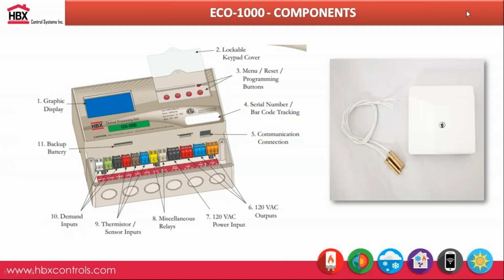In terms of key components on the 1000, as you see, we have a full graphic display. The nice thing about the Eco 1000 is that everything's on 1 or 2 screens, so we give you a lot of information on one screen. You can see if it's in a heating or cooling demand, you can see if you have additional set points or setback options, and you can see your hot tank, cold tank, as well as the outdoor temperature all in one display. You can also navigate to a second screen, which acts as your system function screen options.